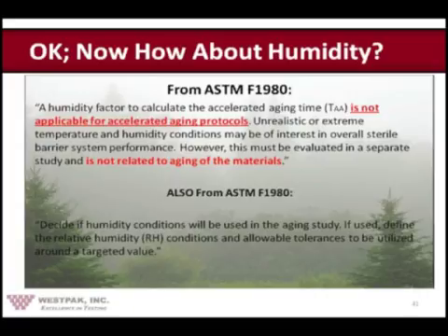But it goes on to say, decide if humidity conditions will be used in the aging study. So it doesn't exclude them. And so it says, if used, define these conditions and the allowable tolerances. Interesting. They're not big on humidity. You can tell that right off the bat.